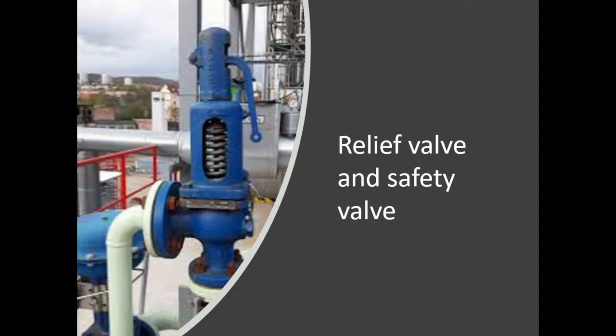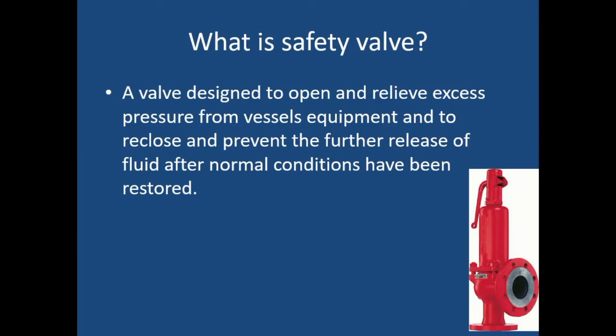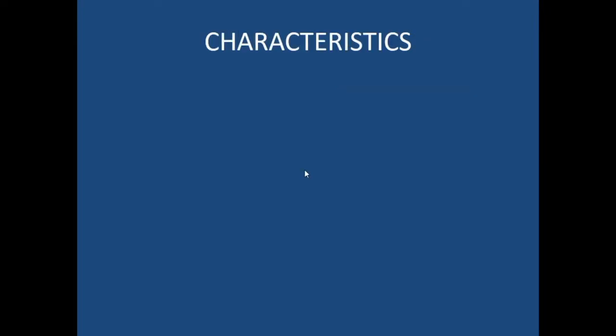Now there is another system — the safety valve — that will give an overpressure indication and also take care of the system. We will see the relief valve video later on. A safety valve is basically designed to release or open the excess pressure available inside the equipment or a vessel. Once it releases the pressure, it will come back to the original position and reclose once the equipment pressure reaches its normal condition. This device is not going to rupture; it will release the pressure and reclose, allowing the plant to function properly.